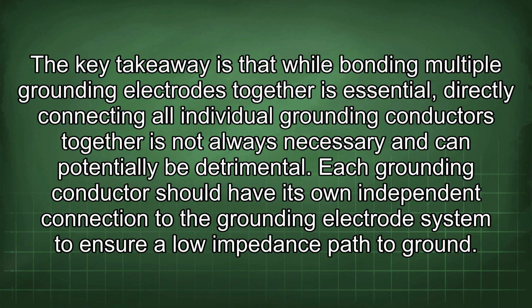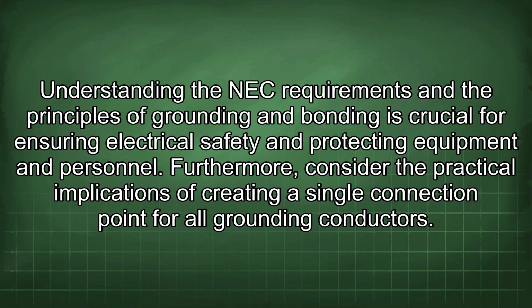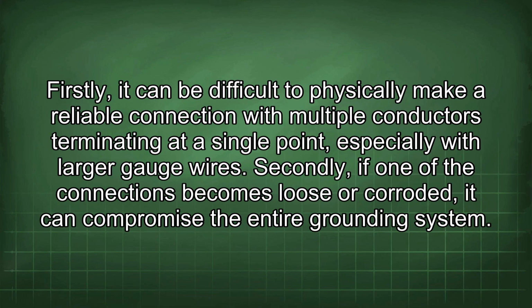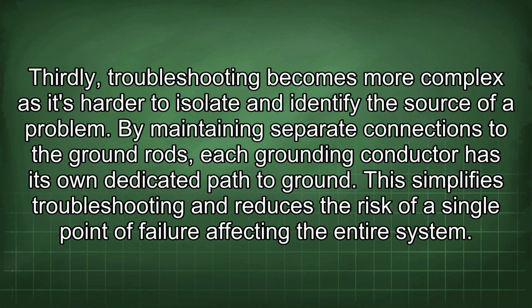Each grounding conductor should have its own independent connection to the grounding electrode system to ensure a low impedance path to ground. Understanding the NEC requirements and the principles of grounding and bonding is crucial for ensuring electrical safety and protecting equipment and personnel. Furthermore, consider the practical implications of creating a single connection point for all grounding conductors. Firstly, it can be difficult to physically make a reliable connection with multiple conductors terminating at a single point, especially with larger gauge wires. Secondly, if one of the connections becomes loose or corroded, it can compromise the entire grounding system. Thirdly, troubleshooting becomes more complex as it's harder to isolate and identify the source of a problem.